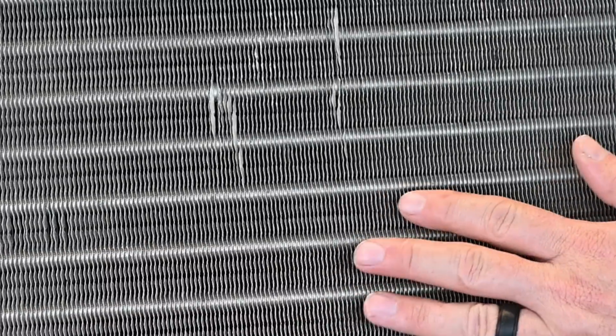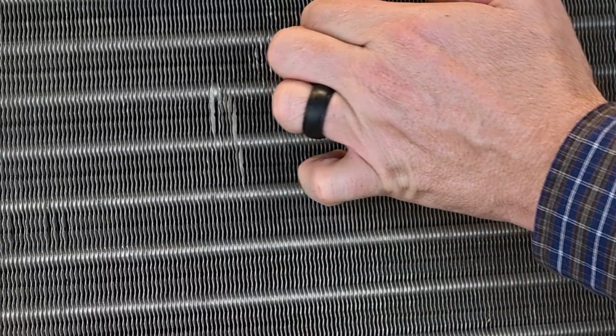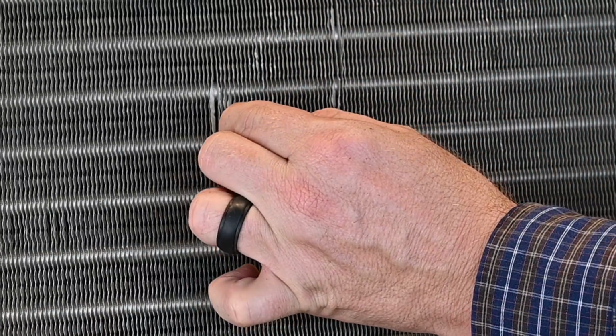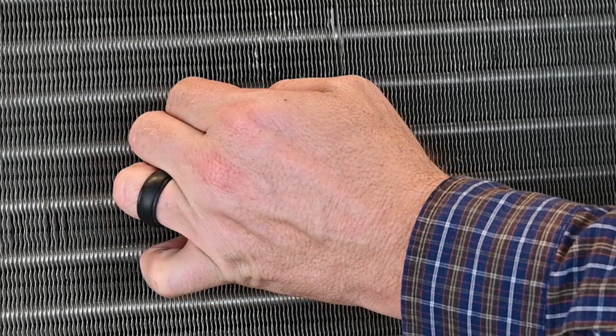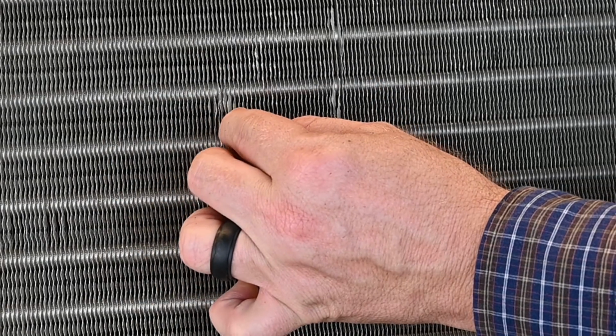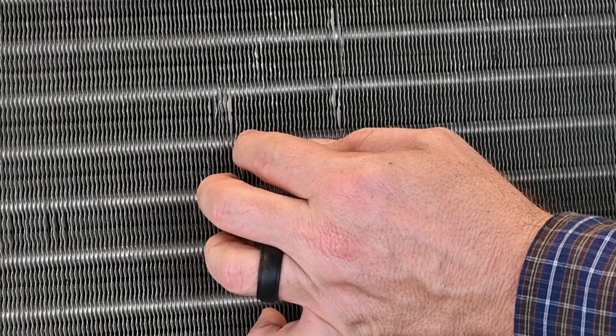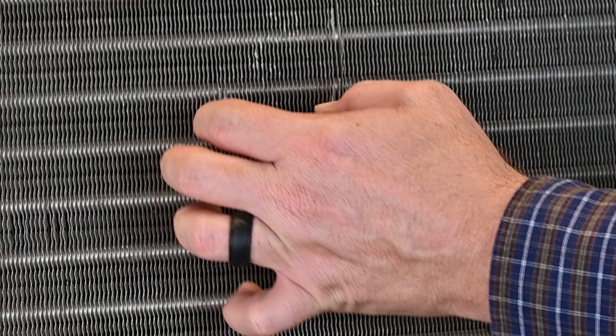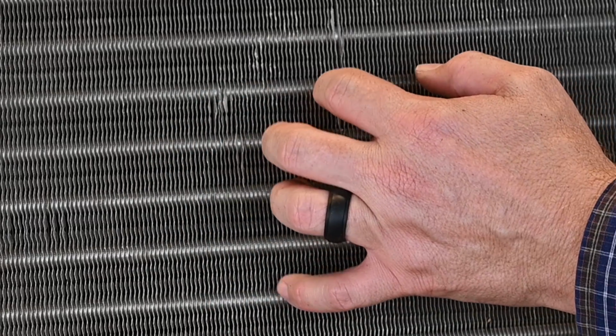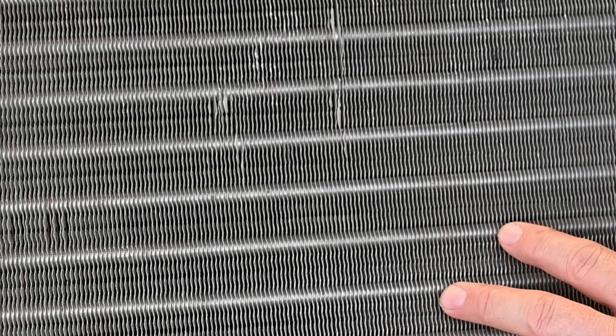So here's a good example of what our evaporator should be. Even these little damages like this on the bottom side could cause that water to drip off of it at that point. Now, many of these are easy to fix. We can use a fin comb tool or a type of butter knife to kind of straighten some of these up, which are not too bad. But on the bottom side, it can cause water to drip out.